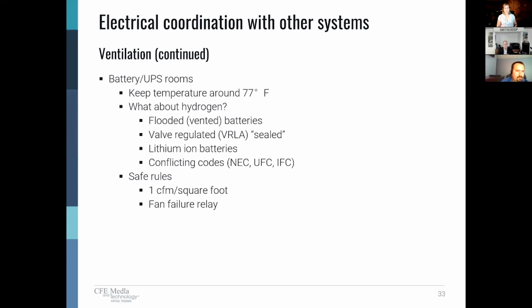So battery UPS rooms. This is another area where these are even more temperature sensitive, particularly in the traditional lead acid, valve regulated type batteries that are still being used quite frequently. Those have to be kept at about 77 degrees Fahrenheit max. That's because the life of the batteries will decrease significantly if it gets warmer than that. So watch the temperature on those rooms. A lot of the old inspectors and a lot of the old codes are concerned about hydrogen. You see a lot of discussion about hydrogen removal, ventilation systems. Typically the sealed batteries that are used today don't require this, versus the old flooded ventilated batteries that you see sometimes in some facilities. Again, this is going to be a discussion with the local authority.